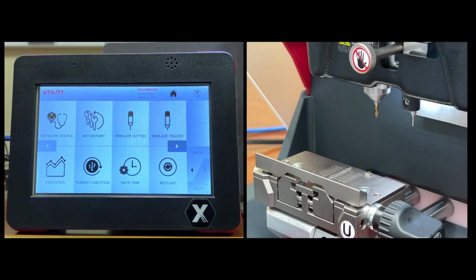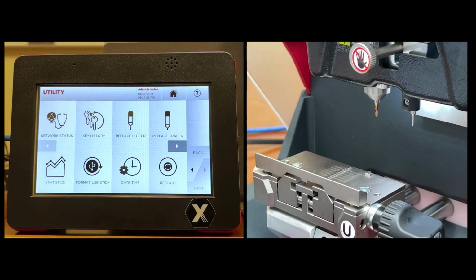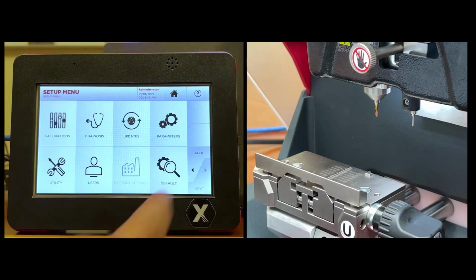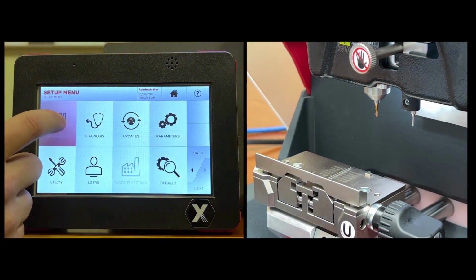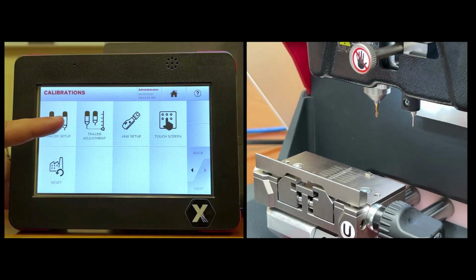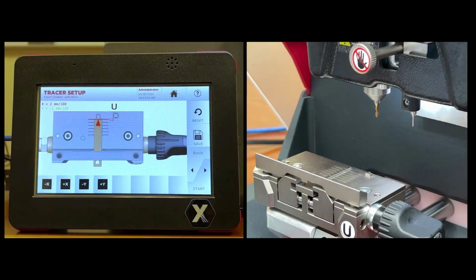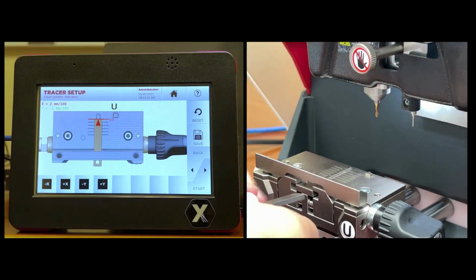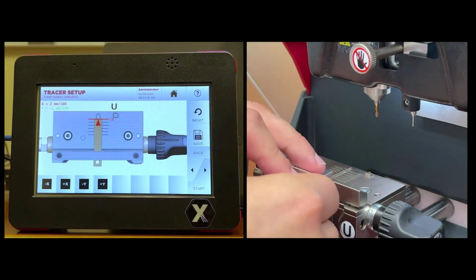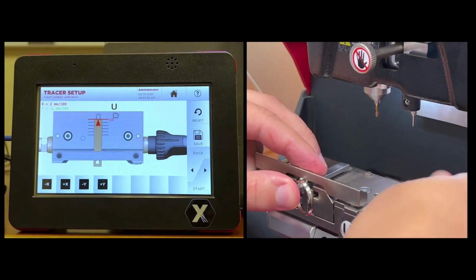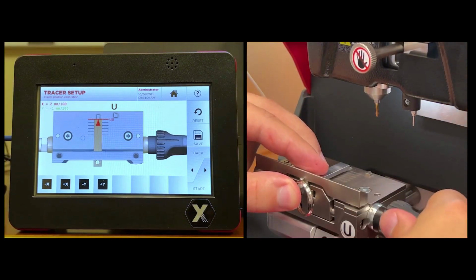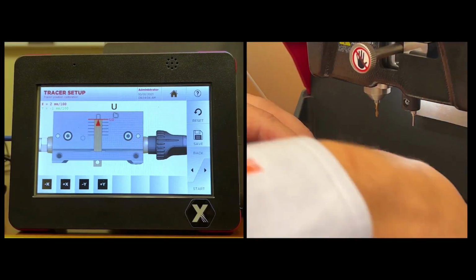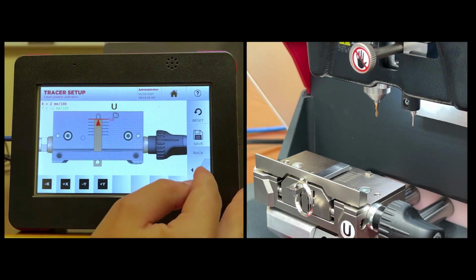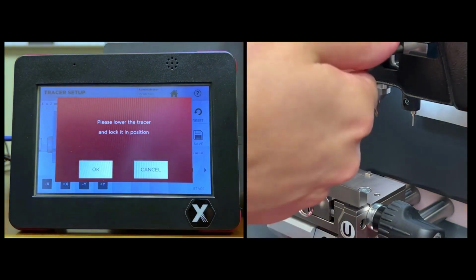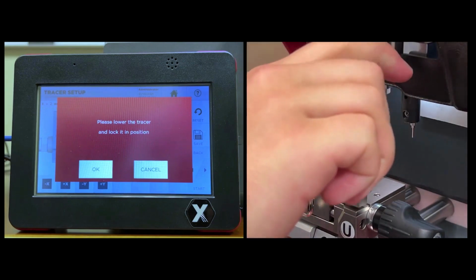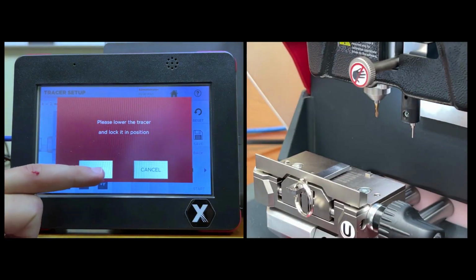Then hit OK. Once the tracer has been replaced, we have to do some calibrations. Hit Back, go to Calibrations, then do Tracer Setup. First, you will need to insert the calibration template. Insert it all the way and lock it in place. Hit Start on the screen and then lower the tracer knob. Unscrew it and let it go all the way down. Hit OK on the screen.